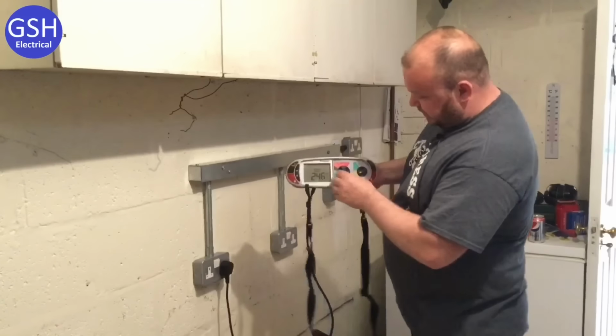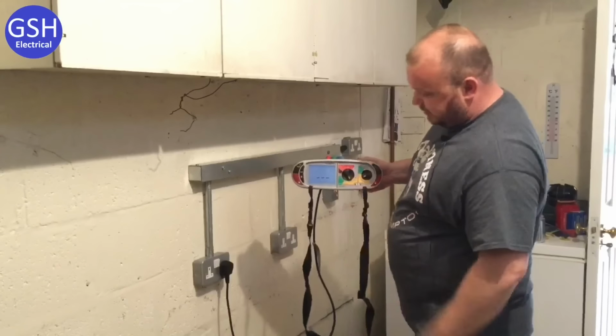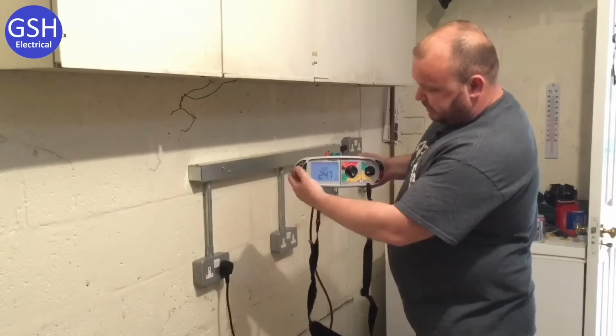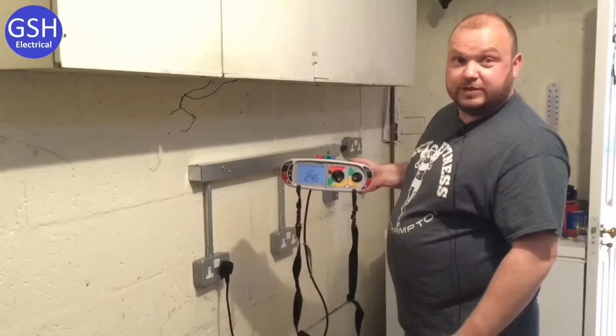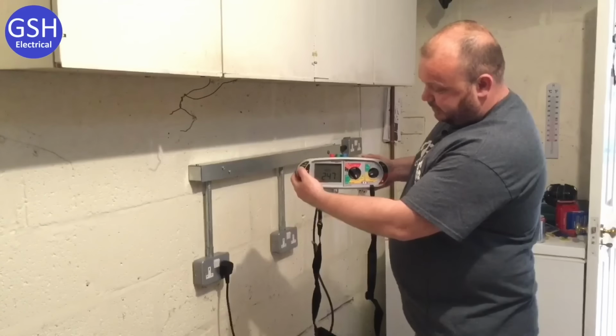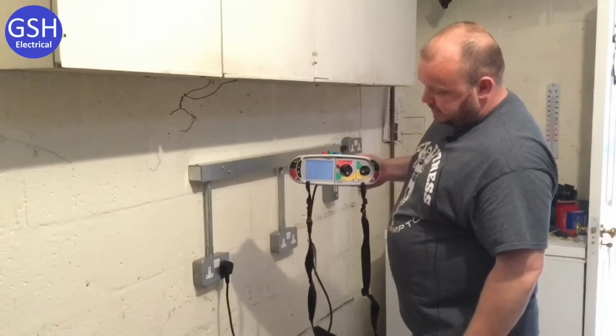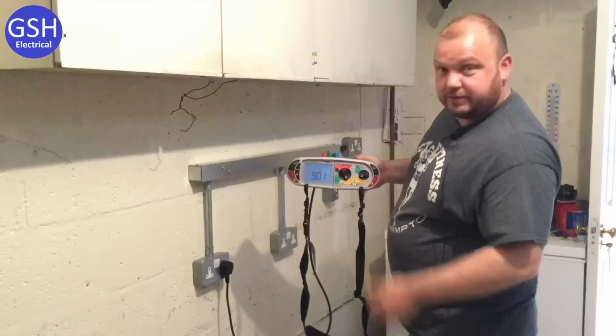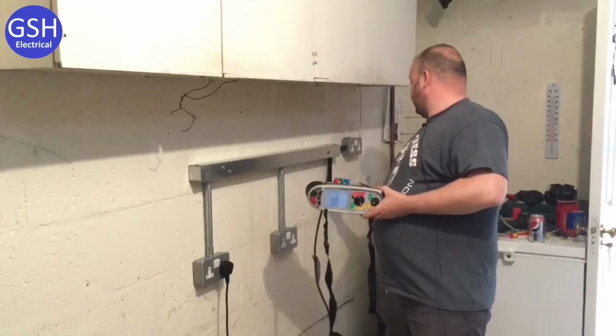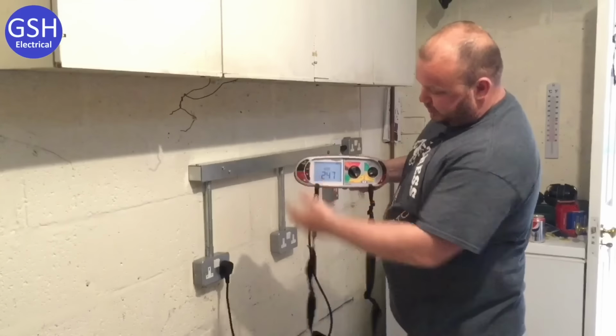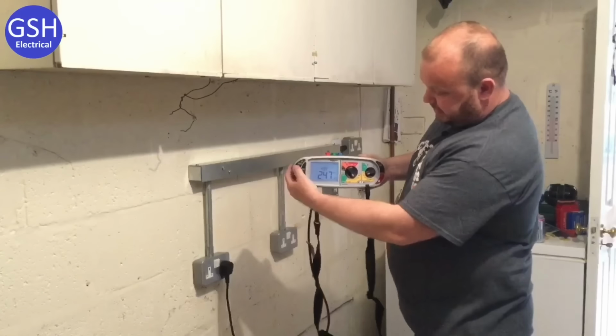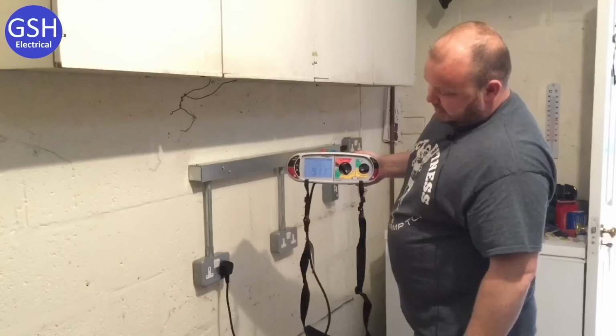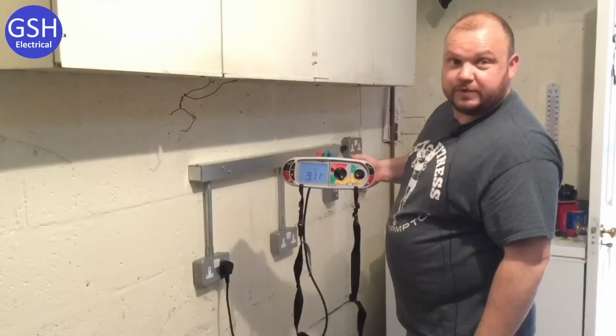Brilliant. Then I'm going to go to 5 times. Okay, and now what is the maximum disconnection time? Maximum disconnection time is 40 milliseconds. Okay, let's see what we get. So I'm going to, there we go, 9.01. Okay. Reset the RCD, change it to 180 degrees. Brilliant. And then test again. 9.11. Of those two readings, which one will we record? Record the highest reading of those two.